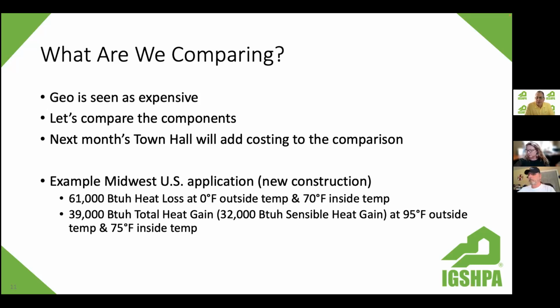So I started with an example in the Midwestern part of the US, new construction, and I picked some numbers that are fairly typical. 61,000 BTUs per hour heat loss at 0 degrees outside and 70 inside, 39 total heat gain with 32 sensible heat gain at 95 outside and 75 inside. So my comparisons are based upon this typical installation.